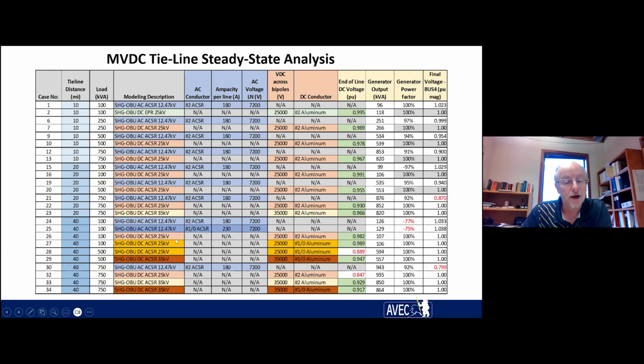Then at 25 kV DC, for 100 kVA of load, the voltage at the end of the line drops about 2%. As you go up in kVA, at 500 kVA with 25 kV, the voltage drop approaches about 11%. Now the DC voltage can vary pretty significantly without a great effect on power quality.